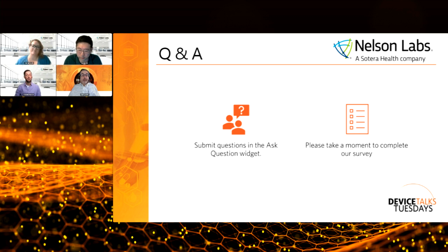All right. I was scrolling around and I had a question here from Johan. Is chemical characterization and toxicological assessment generally expected by the FDA for limited contact devices that come into contact with circulating blood, such as catheters? Go ahead, Lucas. Typically for limited contacting devices with only systemic endpoints like that, you can address those through a combination of in vitro and in vivo tests. Usually, as of now, chemical characterization is used to address the prolonged or the long-term endpoints.